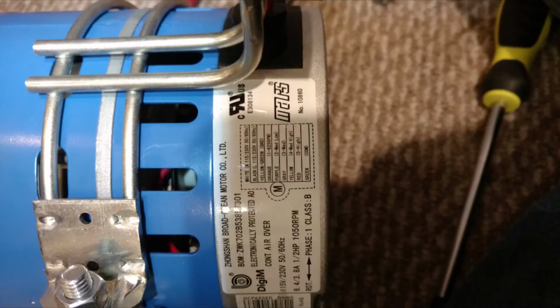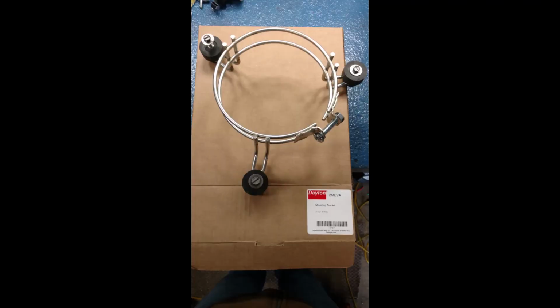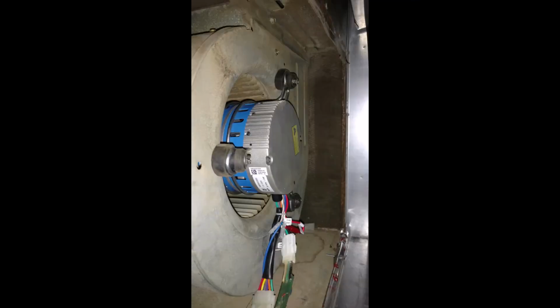So on to the HVAC upgrades. I bought 2 of these energy efficient motors that use a lot less power from a company called Mars. A 1/2 horsepower one for the furnace blower and a 1/3 horsepower one for the outdoor condensing unit. These are so-called rescue motors that HVAC techs can keep on their trucks so that they can get someone up and running quickly if they don't have the exact match parts. They also happen to save much energy compared to a typical permanent split capacitor motor.